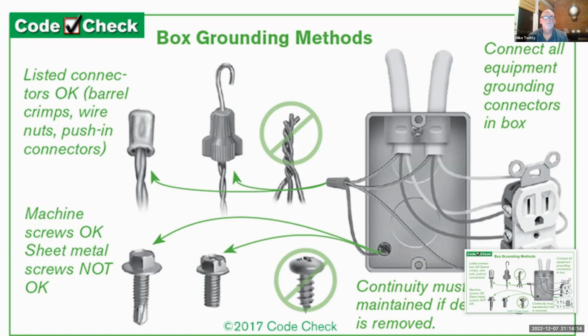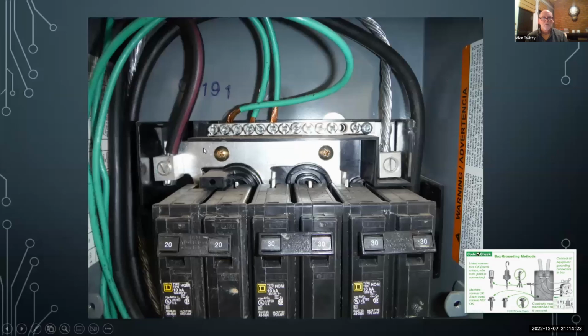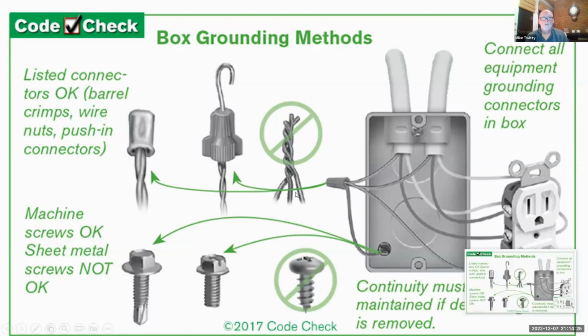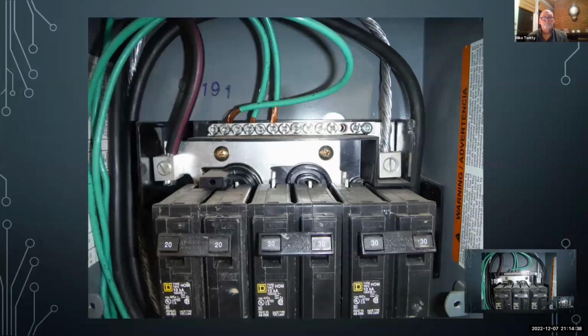Like I say, I did a compliance inspection last week and that wasn't done. We kind of let them slide on it, just told them to hook them up. But they should be wrapped together like here, and then this will attach to the equipment ground screw on the receptacle when it's installed. They're supposed to be made up at the rough-in stage for that inspection.